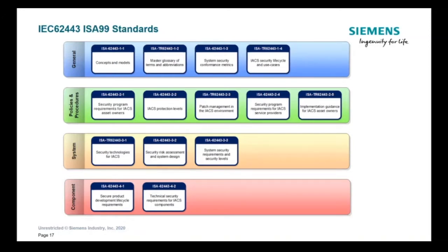So I'm going to start from the bottom here. IEC 62443-4 is all focused on the development and the life cycle maturity models and everything else for product development. So when, for example, military wants to buy a product that has IEC 62443 on those products, they're going to look for stamps or certifications from somebody that has the ability to audit Siemens based on the IEC 62443-4 framework.